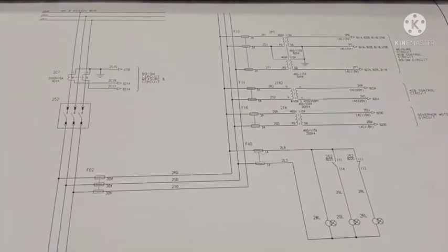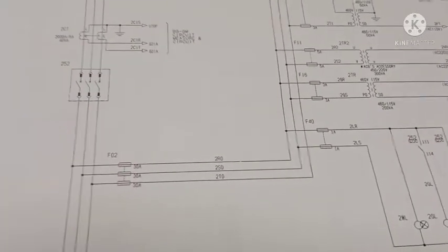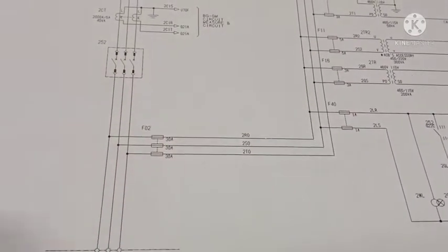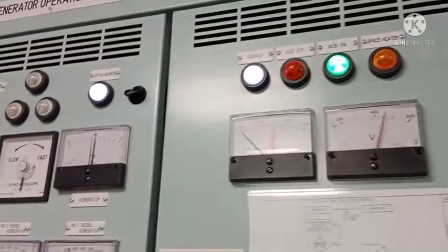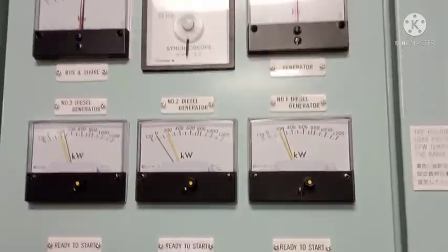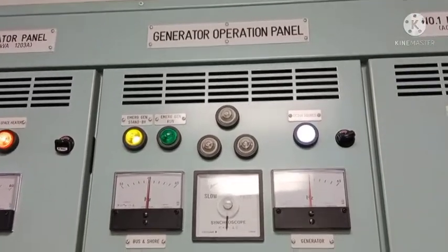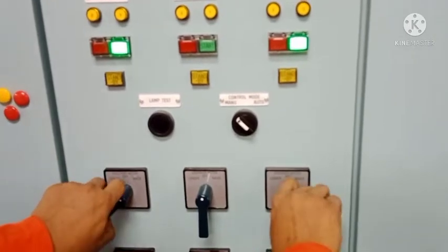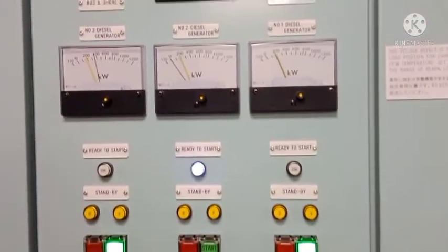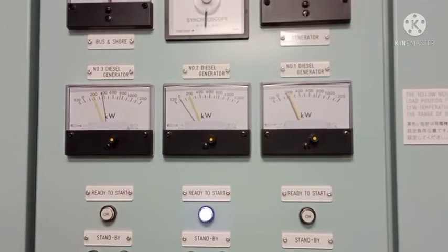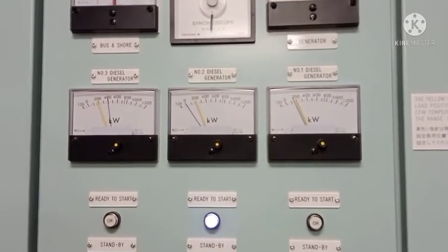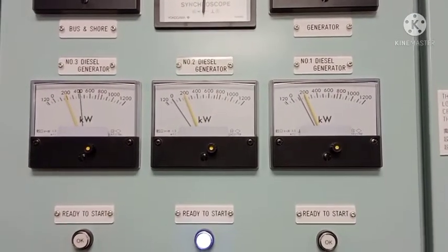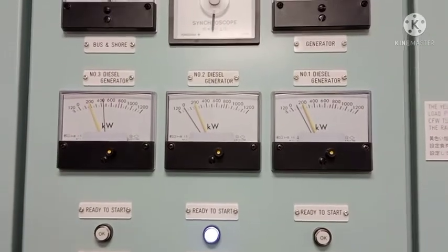Now I am coming to the circuit diagram. This is our electrical diagram. I am checking the voltage when the generator is in off-load condition. I am offloading one generator at a time so I can check the off-load voltage — how much voltage it is producing without load. I want to check each generator one by one to figure out which generator has an issue.